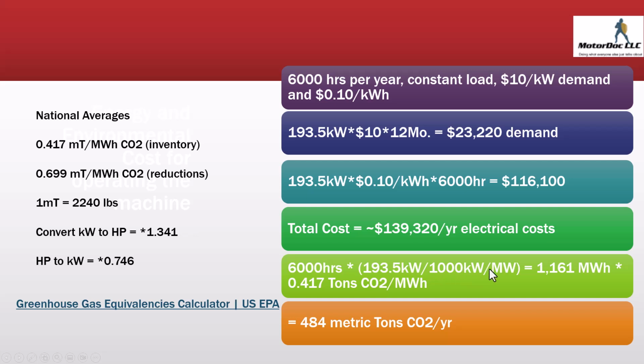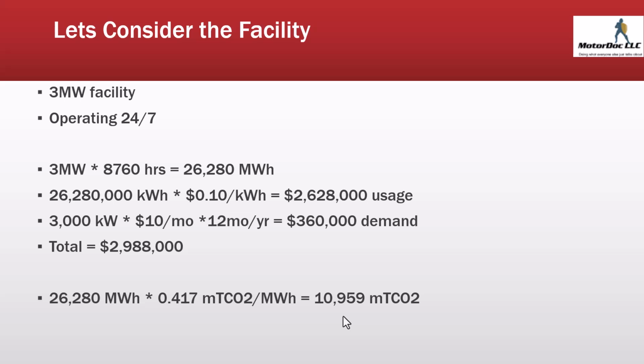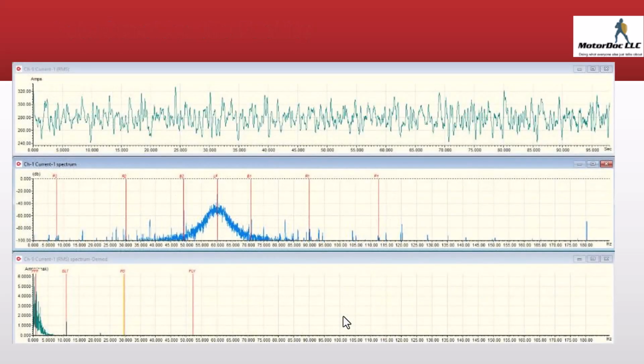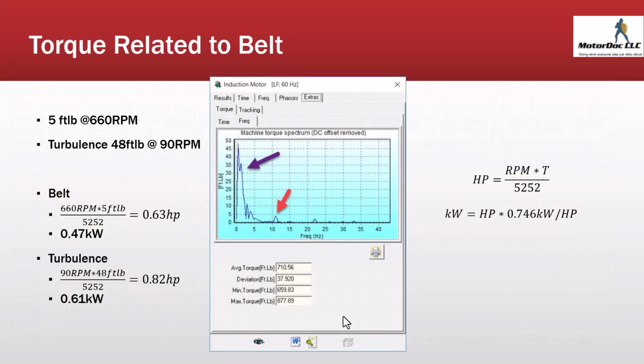Now, if I convert it over to megawatt hours, that would be 1,161 megawatt hours, which would be an inventory of 484 metric tons of CO2 to run just that one motor per year. So if I look at a facility, let's say we use a 3 megawatt facility, and let's just say it's 11,000 metric tons of CO2. Now let's start taking a look at some machines in that facility. So we take a look at a belted application, and we can convert torque readings. I'm going to show you direct kilowatt readings in a minute, but we can convert this just by looking at RPM times the foot-pounds at that point, dividing by 5252, and that gives us watts or kilowatts.